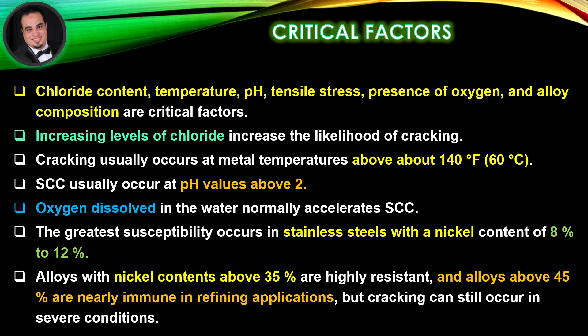Oxygen dissolved in the water normally accelerates stress corrosion cracking. The greatest susceptibility occurs in stainless steels with a nickel content of 8% to 12%. Alloys with nickel contents above 35% are highly resistant, and alloys above 45% are nearly immune in refining applications, but cracking can still occur in severe conditions.